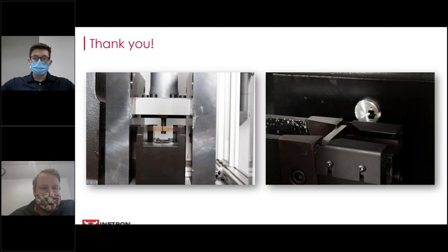Thank you. The next question was, do manual systems pass today's safety standards? And I think they mean a system like the one you showed earlier with the big round dial. Yeah, a good question. We certainly recommend that you perform your own internal safety audit. But in terms of passing standards, we can't speak for other providers. A common machine safety standard I can think of is ISO 13849. I believe that's the machine moving parts standard. The MPX does comply with this standard. But again, we can't speak for other motorized enclosed systems in general. But good question.